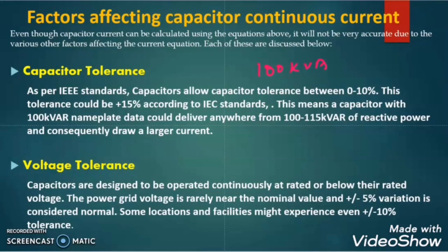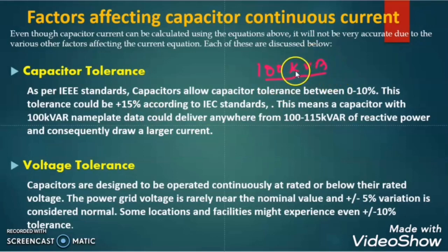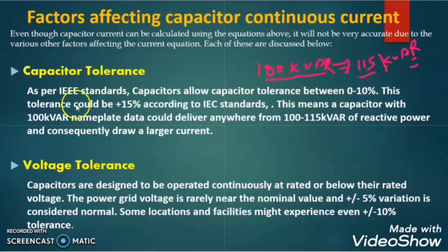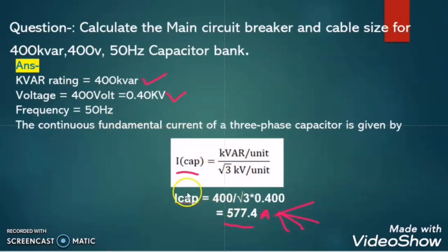Let us explain these one by one. As per the IEEE standard, the capacitor tolerance is between 0 to 10%, and as per the IEC standard the capacitor tolerance can be up to 15%. Suppose we have a 100 kVAR capacitor — due to its tolerance, this capacitor can behave as a 115 kVAR capacitor. So if I place a capacitor bank rated at 100 kVAR but with 15% tolerance, it will behave like a 115 kVAR capacitor. When this value changes, the capacitor current will also change.